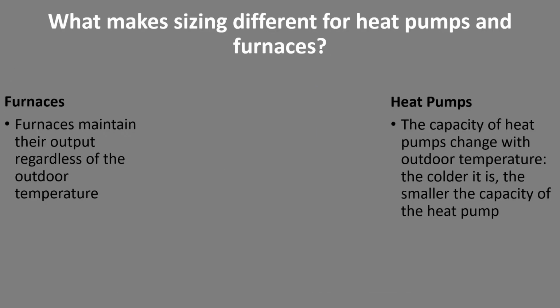What makes the difference in sizing between heat pumps and furnaces? Well, the big thing about furnaces, they maintain their output regardless of the outdoor temperature. When it's 50 degrees outside, they have the same output as when it's 0 degrees outside. Heat pumps, on the other hand, change with the outdoor temperature. The colder it is, the smaller the capacity of the heat pump. And I do realize there are new cold climate heat pumps on the market, extended capacity heat pumps, if you will, but they still respond to the outdoor temperature in interesting ways, and we need to take a look at their detailed capacities also.